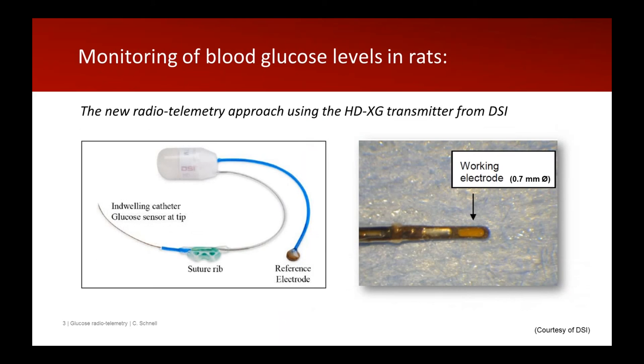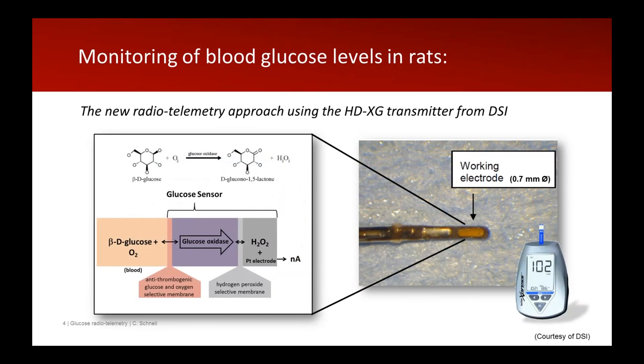We have been using the DSI device for remote glucose monitoring in rats for about six months. As already shown, it has a reference electrode and a glucose sensor at the tip — only 0.7 millimeters — which fits very nicely in the rat artery. The chemical reaction at the tip of the catheter is exactly the same as in a standard glucometer: glucose oxidase. This is important for translation between preclinical and clinical data, as we use the same measurement method, which will enable better comparison between animal and human results.